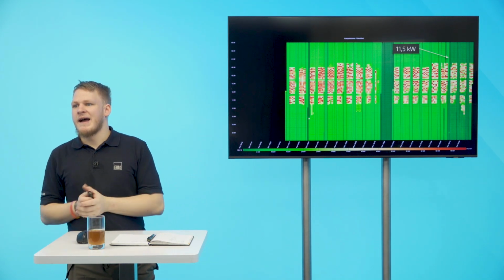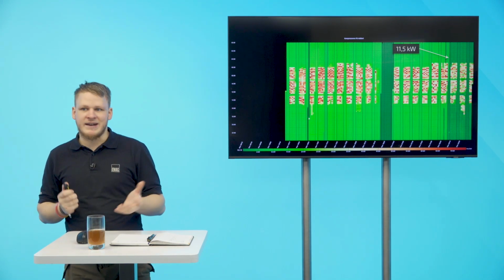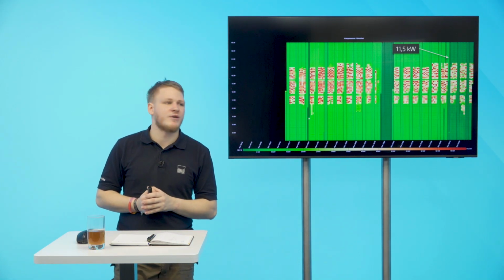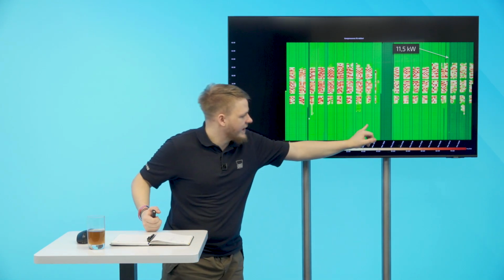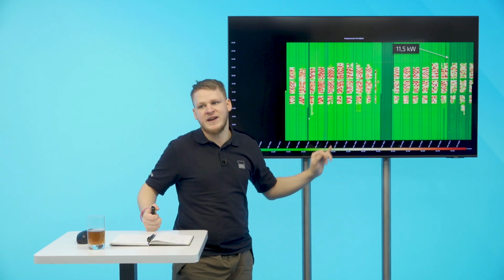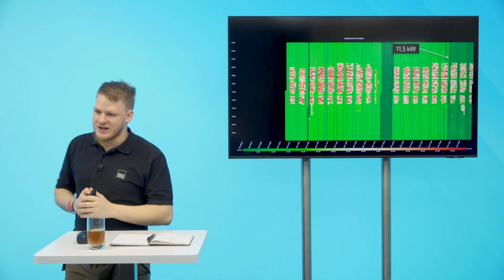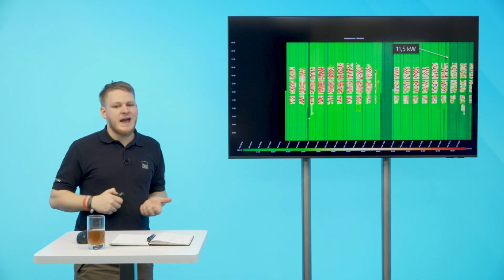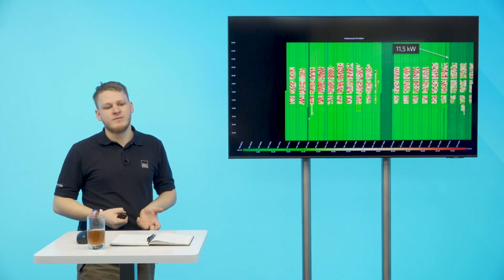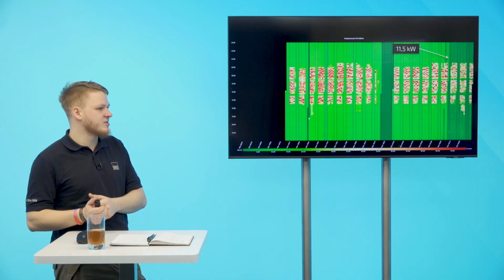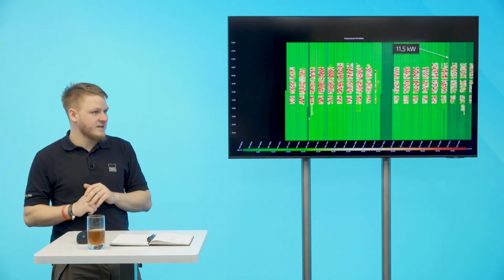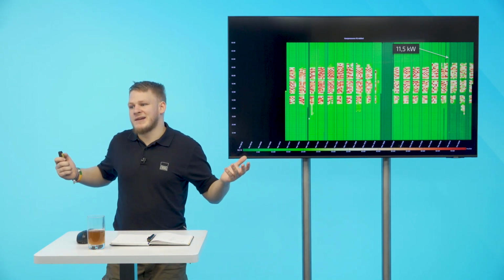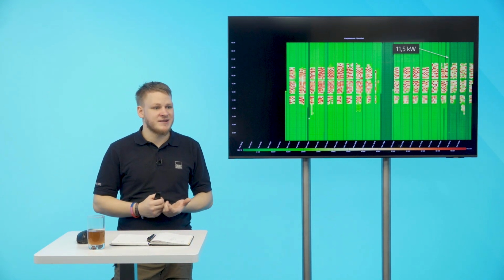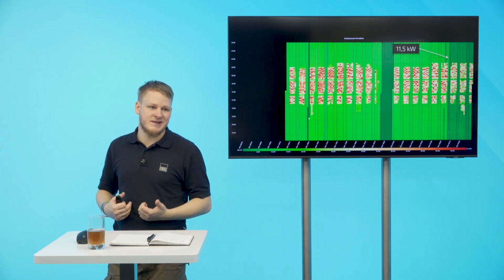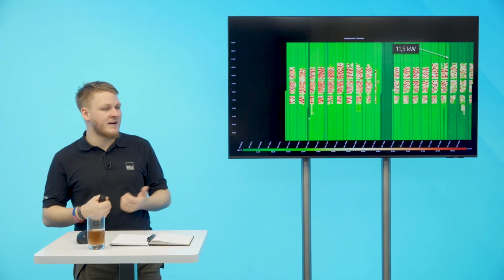I looked at the data and was curious, asking myself why at night we have a consumption of 11.5 kilowatts, shown in the nice light green range here. I asked around whether we had anything else behind that distribution board aside from the compressed air station, and found out that wasn't the case. So it had to be the compressor. It was actually actively running, and I expected it to have no output at all, but it did.